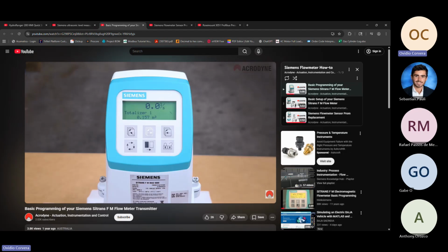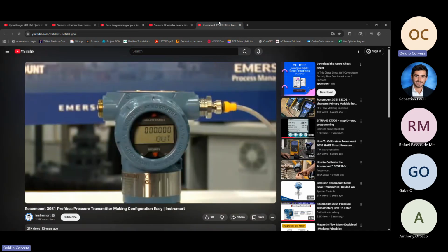For the pressure transmitter, we're providing the Rosemount 3051S pressure transmitter. It's really just used to measure pressure. So it's a very simple instrument. There's not much to it. Any configuration is usually done with the HART communicator to configure most of the settings. You can do some basic setup with the buttons at the top of the transmitter. So this video goes through how to do very basic configuration of the transmitter.